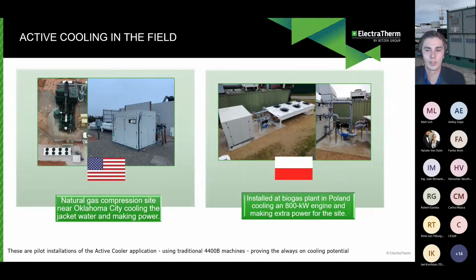So in the field, active cooling is becoming very popular across the globe. On the left here, we've got a natural gas compression site near Oklahoma City that's cooling the jacket water and making power. And the unit installed on the right is at a biogas plant in Poland. They're actually using exhaust heat too in that system to make power, and they make a considerable amount of power for that site. Another thing I'd like to add about the site in Oklahoma is that it was a site with a PTO-driven fan and a 5-circuit radiator.